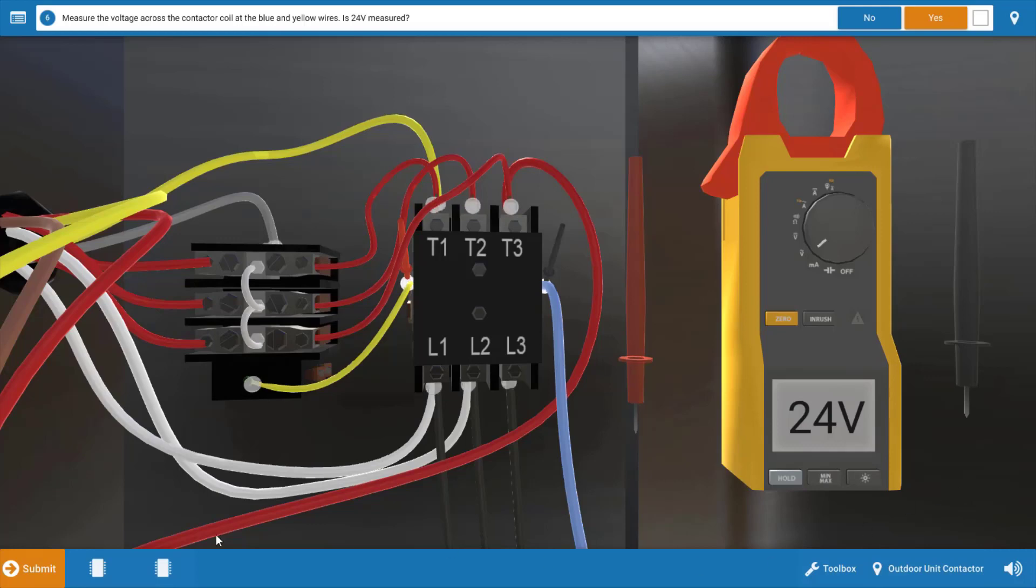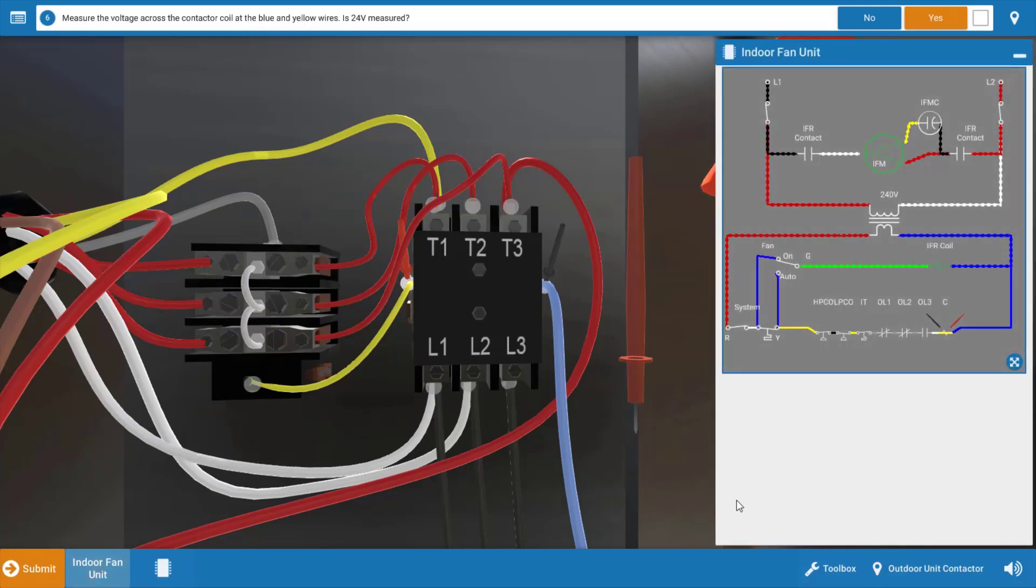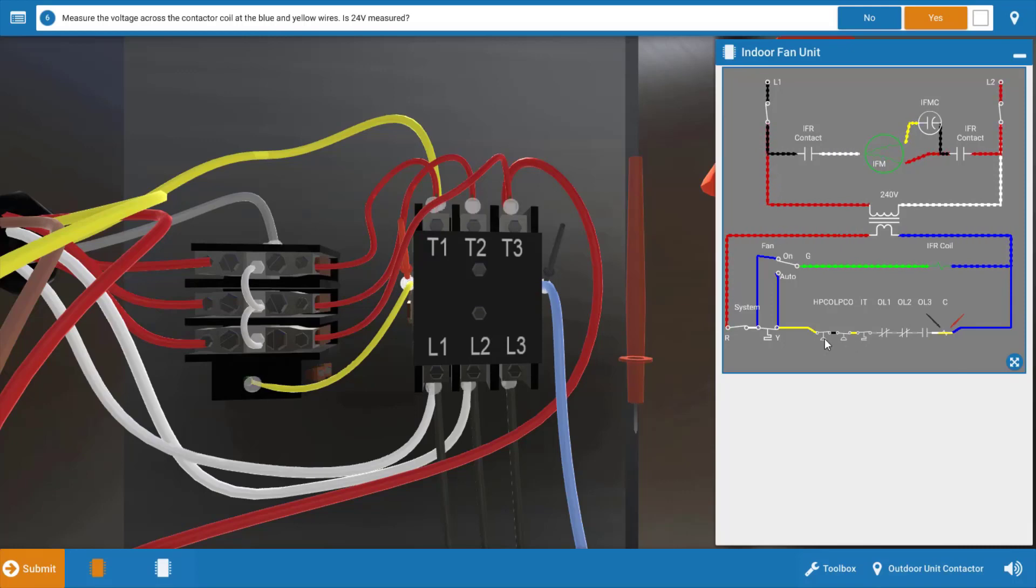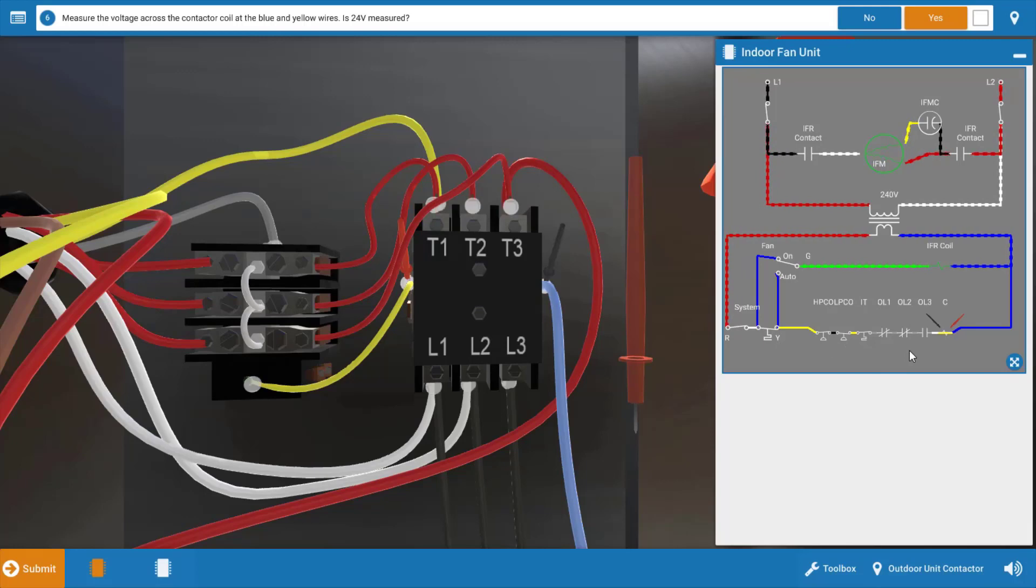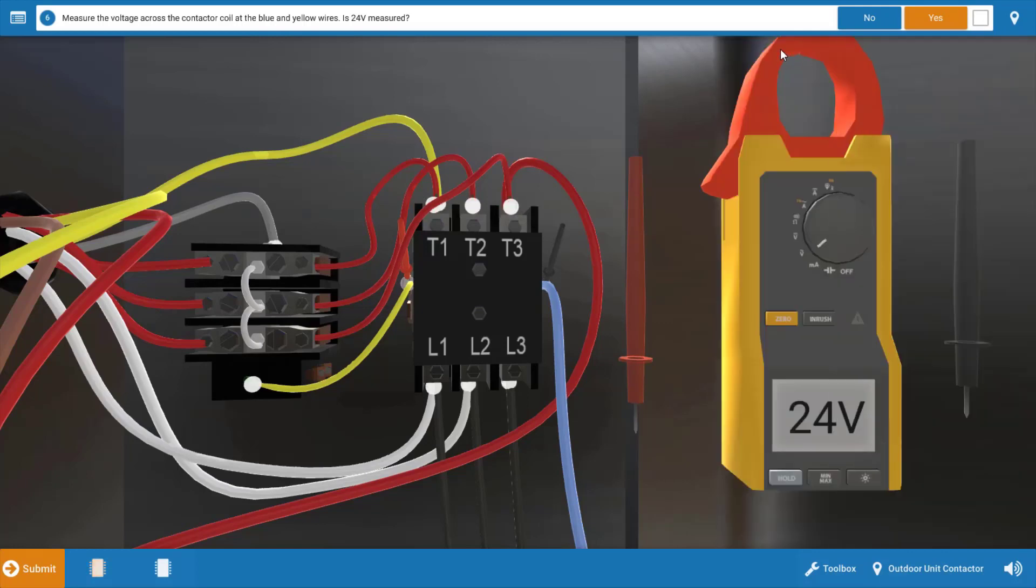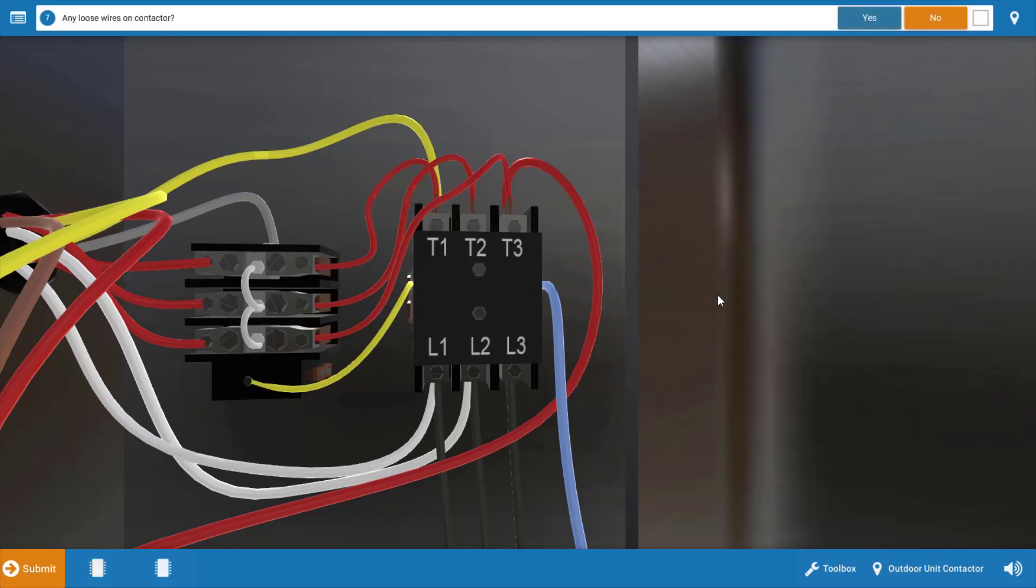Now, if you're not clear about that, let's take the diagram back out again and take a look. We can see that our meter leads are placed right at the contactor coil, and we're receiving 24 volts there. So that verifies that all these safety switches, as well as the thermostat, are closing their contacts, and the contactor coil is receiving power. Now, this most likely means the contactor's faulty. So go to the procedure guide, and we do measure 24 volts, so we can click yes.